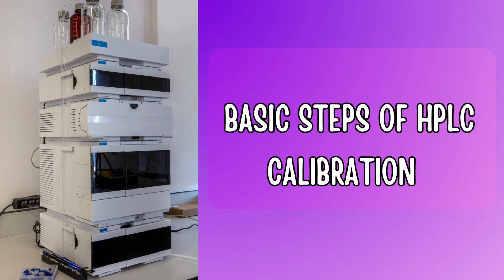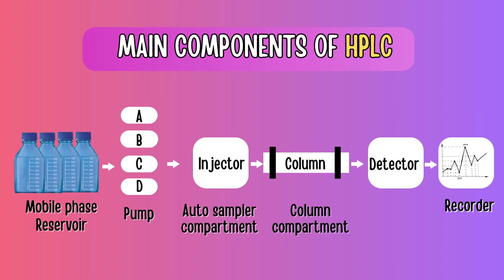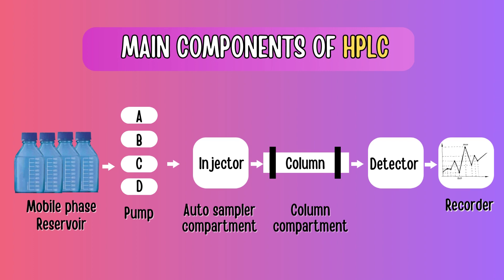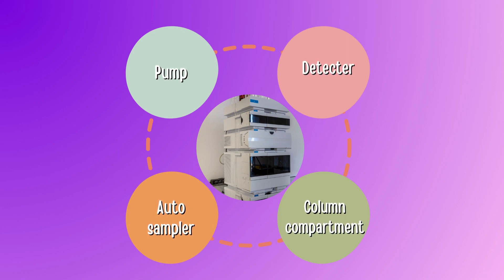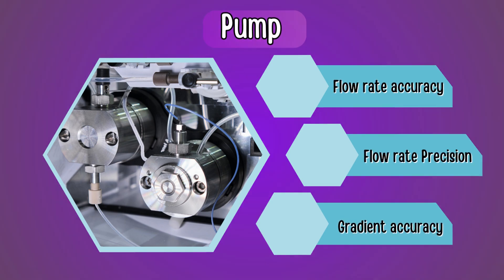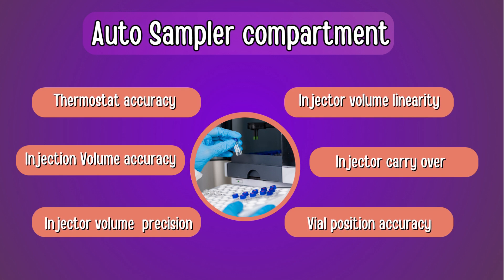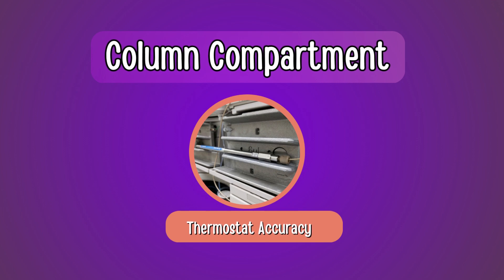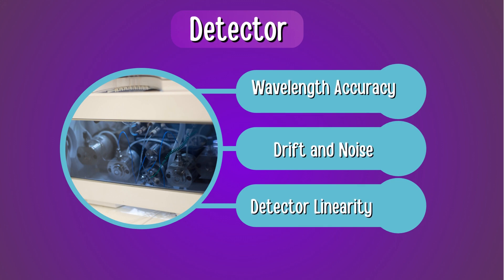In this video, I will explain the basic steps of HPLC calibration. The main components of an HPLC system are Mobile Phase Reservoir, Pump, Auto Sampler Compartment, Column Compartment, Detector, and Recorder. Tests carried out during HPLC calibration for UV and PDA detectors include pump-related tests: Flowrate Accuracy, Flowrate Precision, and Gradient Accuracy. For the Auto Sampler Compartment: Thermostat Accuracy, Injection Volume Accuracy, Injector Volume Precision, Injector Volume Linearity, Injector Carryover, and Vial Position Accuracy. For Column Compartment: Thermostat Accuracy. For the Detector: Wavelength Accuracy by Caffeine, Drift and Noise, and Detector Linearity.